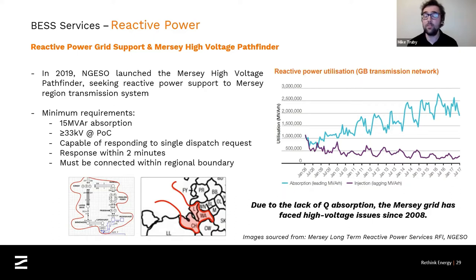The other contract went to a shunt reactor, a traditional mechanism for managing reactive power. We'll come on to why in a moment, but the benefit of a battery energy storage system, unlike a shunt reactor or a STATCOM or something else, is that it is not just there for giving you reactive power services. We can also provide other system actions that Simon's already described, in terms of active power management and frequency response, in addition to that reactive power service. So it's multifunctional, and that means it's better value for the customers of National Grid.